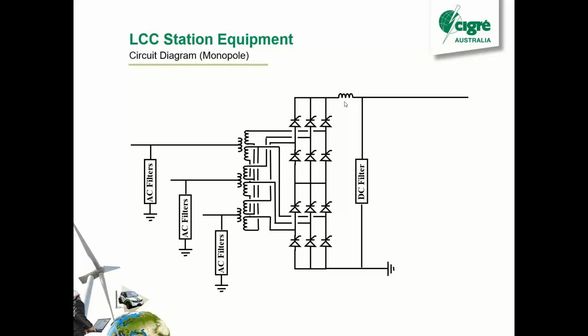So it's not too bad. But if we double the smoothing reactor, we could maybe reduce it to 25 or something like that. So that's one of the key design characteristics for the smoothing reactor. And then last but not least, we have the DC filter. That helps out with your DC voltage.